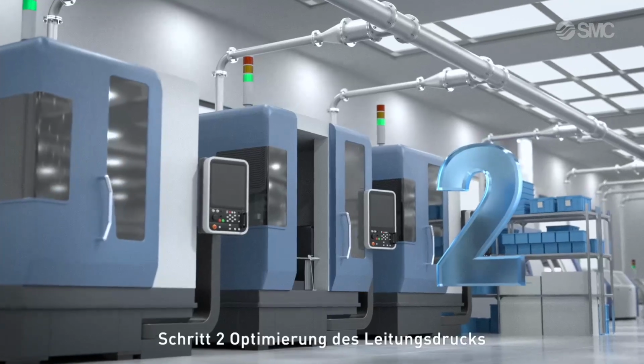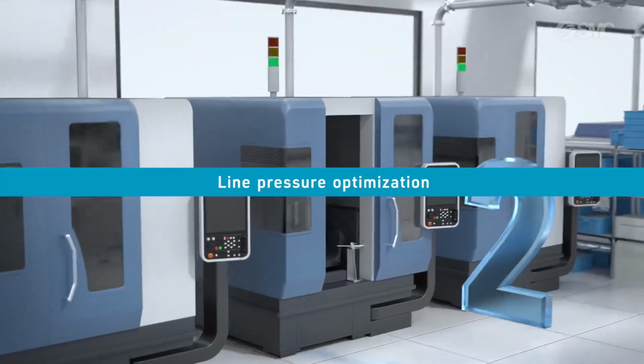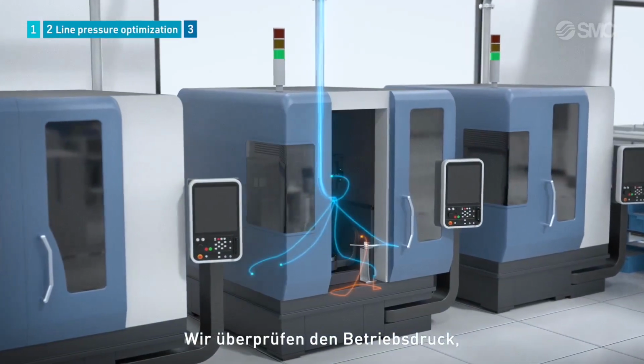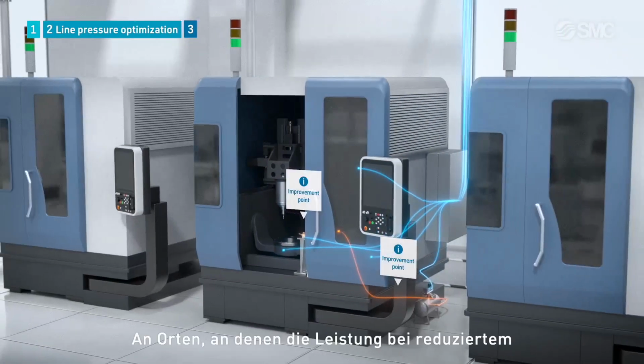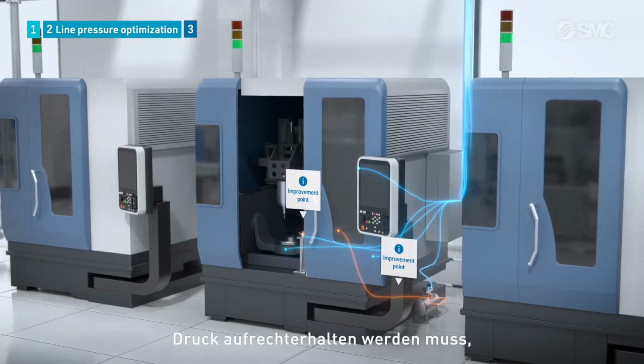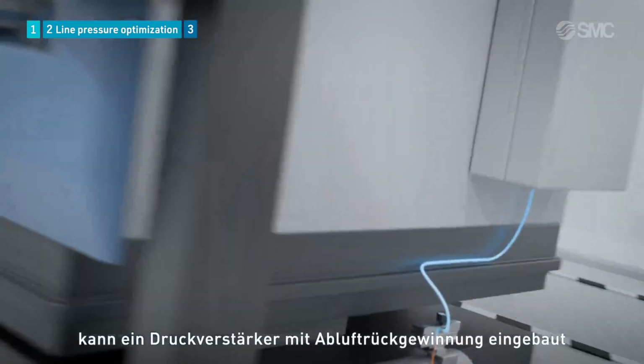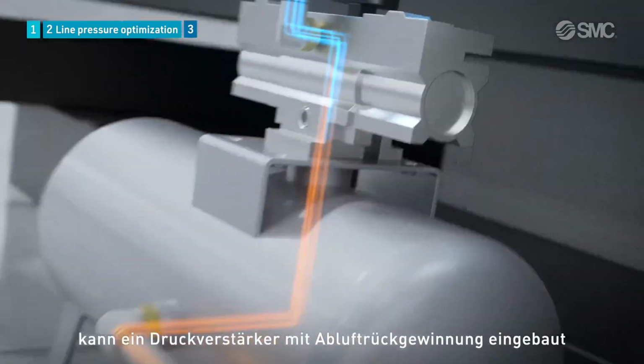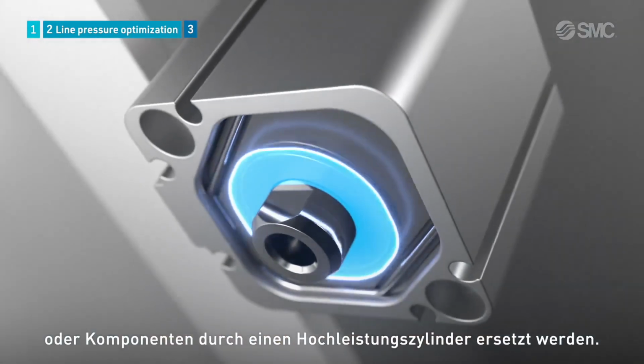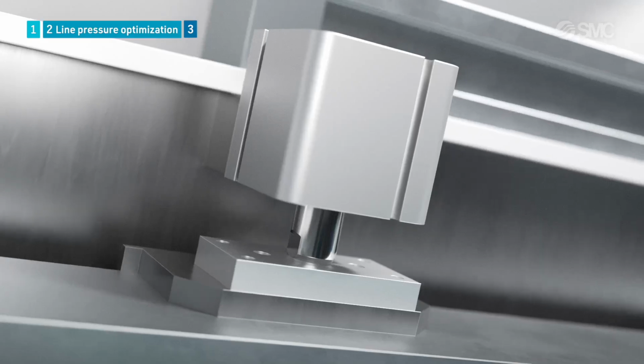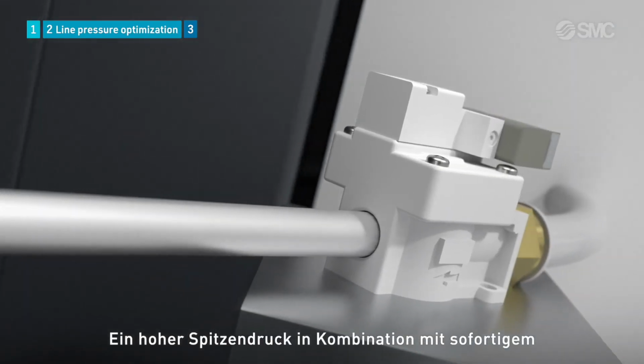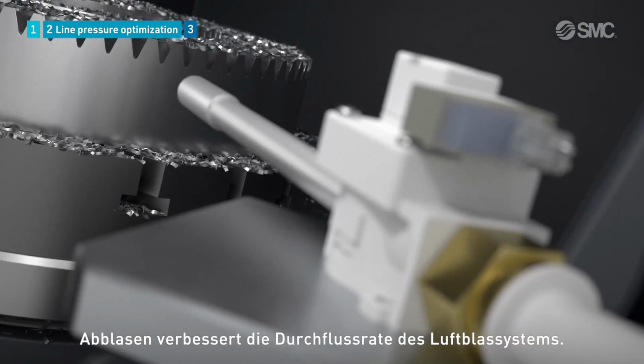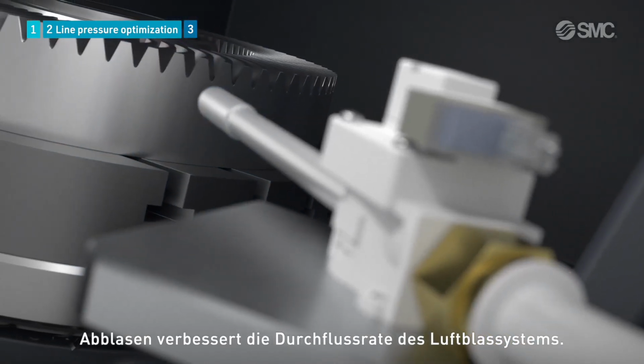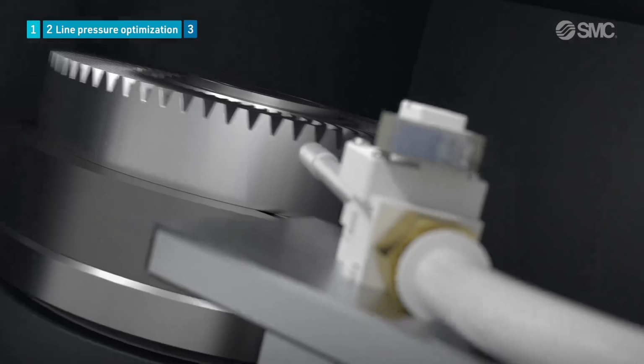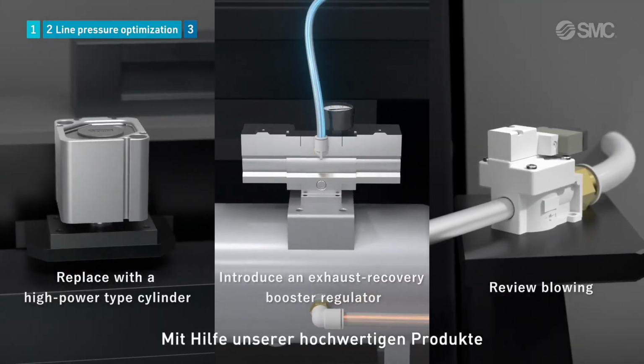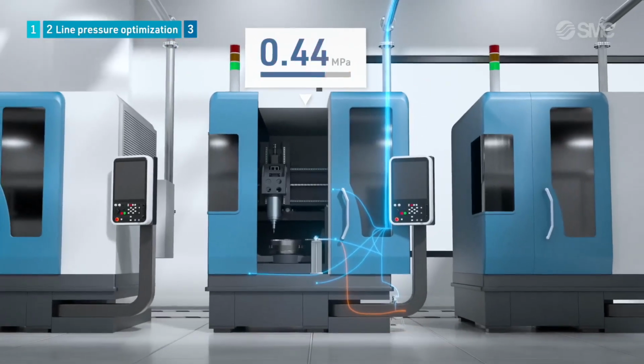Step 2. Line pressure optimization. We verify the air pressure that can maintain production efficiency. In locations where the output must be maintained while the pressure is reduced, we can introduce an exhaust recovery booster regulator or replace parts with a high-power type cylinder. In addition, the flow rate of the air blowing system can be improved by utilizing high peak pressure and instantaneous blowing. By introducing optimal products, we optimize the line pressure.